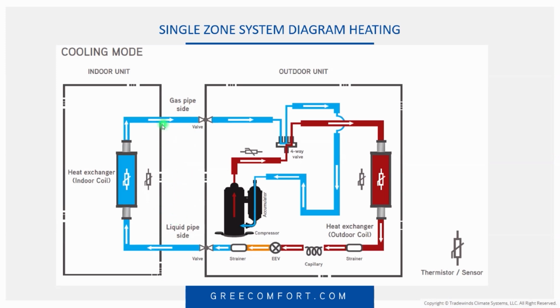The best way to look at this is that it is an extension to the indoor coil. So if that indoor coil is in heating or cooling mode, these two pipes are an extension to that coil, because your metering device is in the outdoor unit. Now the other thing we need to take into account, the way these mini splits work, is you've got that discharge temperature sensor right off the compressor. That is a 50K ohm resistor.